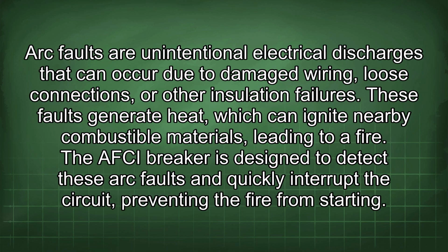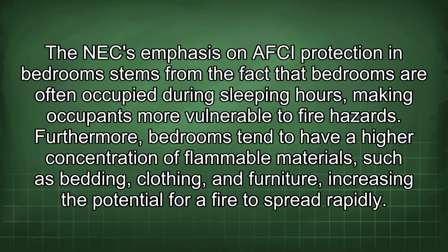Arc faults are unintentional electrical discharges that can occur due to damaged wiring, loose connections, or other insulation failures. These faults generate heat, which can ignite nearby combustible materials, leading to a fire. The AFCI breaker is designed to detect these arc faults and quickly interrupt the circuit, preventing the fire from starting. The NEC emphasis on AFCI protection in bedrooms stems from the fact that bedrooms are often occupied during sleeping hours, making occupants more vulnerable to fire hazard. Furthermore, bedrooms tend to have a higher concentration of flammable materials, such as bedding, clothing, and furniture, increasing the potential for a fire to spread rapidly.